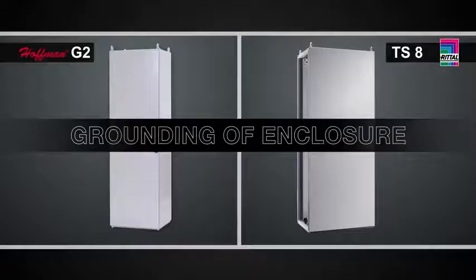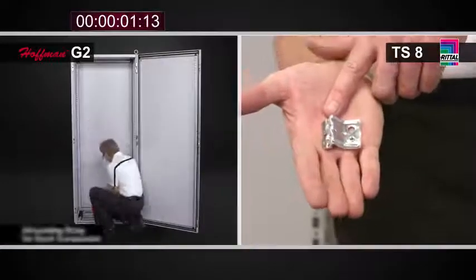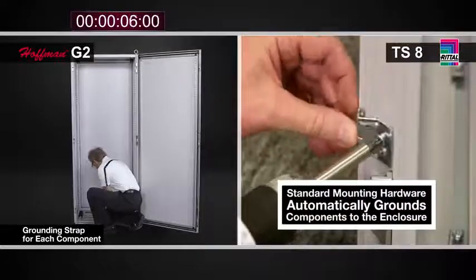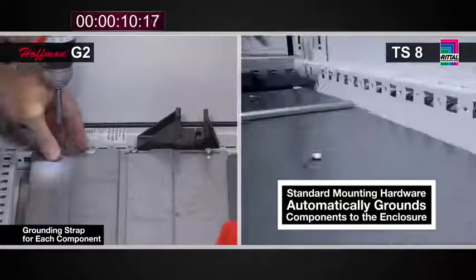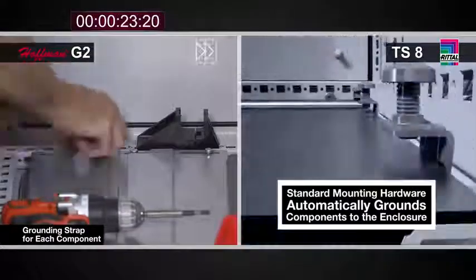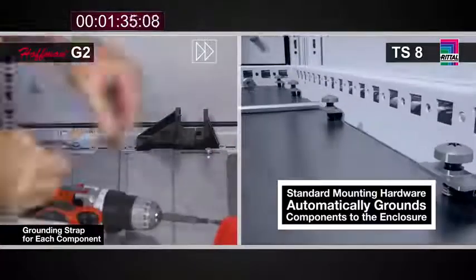One of the most important concerns for our customers, obviously, is safety. This is achieved through best practices and proper bonding and grounding of electrical enclosures. In the TS8, the standard mounting hardware with its grounding teeth provides this bonding back to the frame. Even in the case of the cable entry plates, each individual plate is grounded back to the enclosure. With the G2, every individual panel, including each cable entry plate, has to have its own ground strap and associated hardware to provide the same protection level as the Rittal TS8.